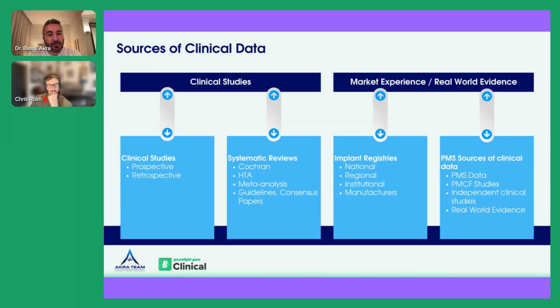And this is the principle which a lot of manufacturers forget to do, and also notified bodies sometimes are pushing manufacturers the wrong way. And like I said, the data is not always one single source, where you just run out and look to studies or look to registries. There is a lot of data out there, and you need to select what would be the best suitable methodology for my device. And then you need to ask yourself, do I need this data, and for how long, and what kind of data do I need?